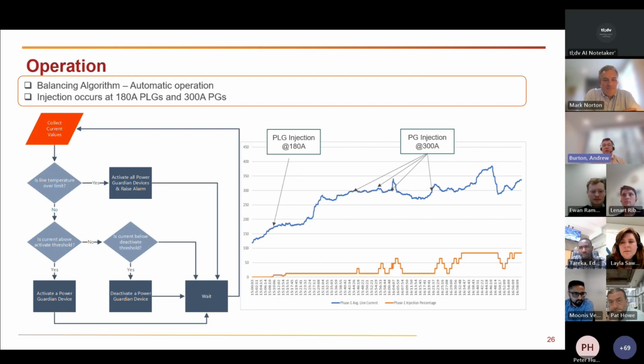So the operation - as I mentioned, the system interaction with our network control. It was more of a light touch from our network control, they just wanted the system to operate automatically. So we introduced an automatic balancing algorithm that looked at when the injection occurs. This is just a demonstration of when it will incur: the power line guardians will kick in at 180 amps, and the power guardians start to inject at 300 amps. So it was just an algorithm to say, if you see this, start to activate the devices. Therefore our network control didn't really have to do too much, just monitor the performance of the device.